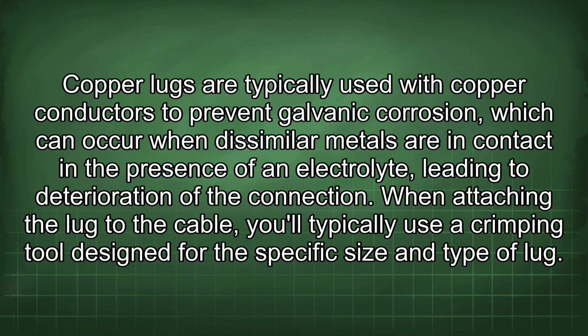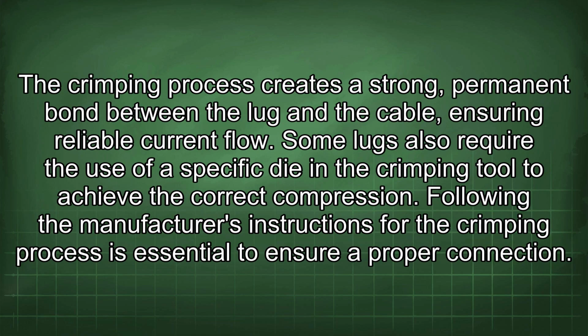When attaching the lug to the cable, you'll typically use a crimping tool designed for the specific size and type of lug. The crimping process creates a strong, permanent bond between the lug and the cable, ensuring reliable current flow. Some lugs also require the use of a specific die in the crimping tool to achieve the correct compression. Following the manufacturer's instructions for the crimping process is essential to ensure a proper connection.